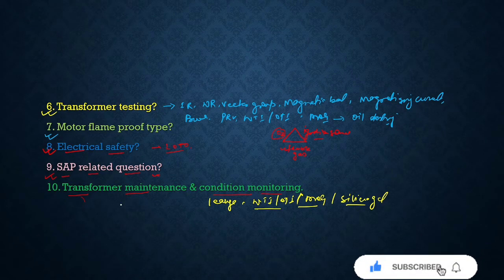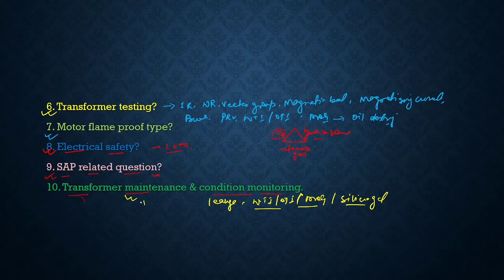And when you take the shutdown of the transformer, what are the maintenance activities you perform? Like we normally check IR, WR, and if NG is installed, then we clean and we check the NG resistance value. Cleaning of the transformer is also included. We also perform functional tests, to check whether these protections are working or not, by looping those protections. So these are the preventive maintenance activities performed if we take the transformer shutdown.